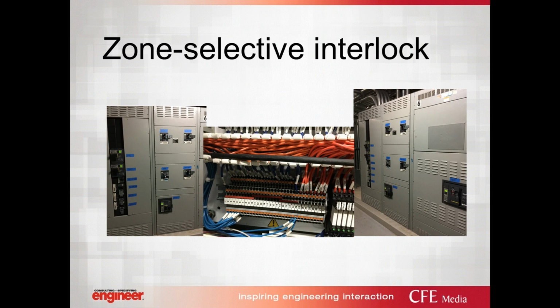If there is a change at some point during the construction of the project and sections of the gear need to be switched or moved in the field, this is going to require a factory field engineer for any corrections, startups, or issues. You can also get zone selective interlocking that has communications connections with systems, so you can follow along and see how your system is doing. It will report back to your building management system. But this is an issue because if you lose that communication, you may not know that your gear is offline. Next to series-rated gear, this has one of the highest considerations for future additions or modifications once the system is completed.